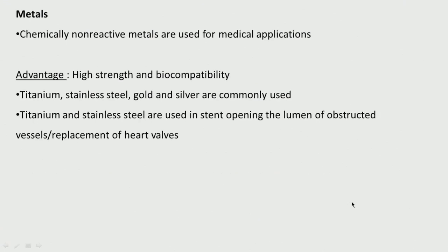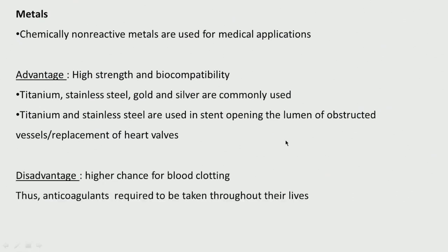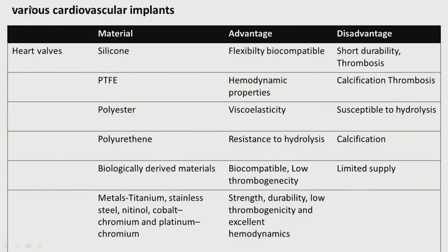Metals are non-reactive and have good strength and biocompatibility — titanium, stainless steel, gold, silver. They are used quite a lot in lead wires. A disadvantage is blood clotting, so they have to be coated with some anticoagulant material or patients have to take lifelong medication to prevent coagulation of the blood.